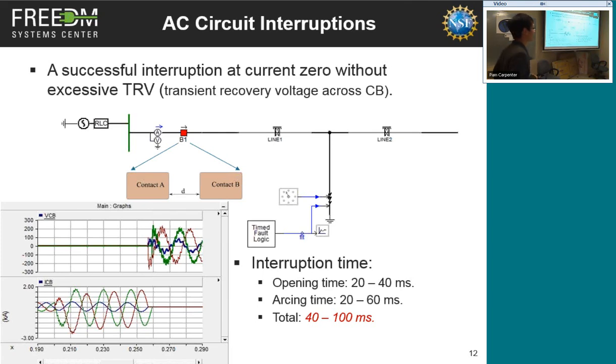And this condition is, in terms of arc, there will be no current, and at that moment there will be no arc. For a very short period of time, there's no arc. And at that time, if you have the capability to withstand the voltage and recover the dielectric strength at that moment, you'll be able to interrupt the circuit. But if you are not, then the current will continue flowing, and you are not able to interrupt the circuit.